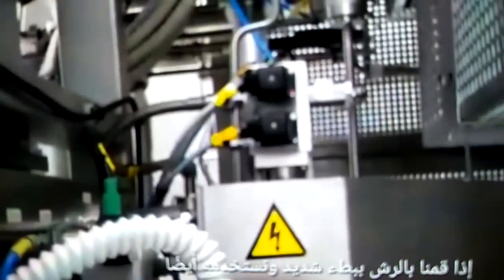So to check all these alarm positions, we have two probes in the center. You see here, we have two probes, one here and one here. These two probes are to check the peroxide levels during spraying. Did we spray too fast? Did we spray too slow? And we also use it for checking the level when we fill. But we'll go through more of this, okay? Then we have two valves here. One valve is for filling hydrogen peroxide. This one here is the filling valve. This pipe here underneath is connected directly to the pump.